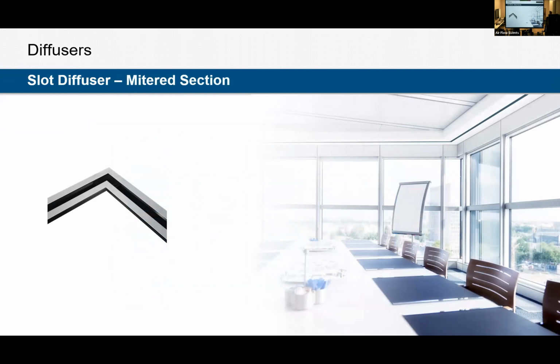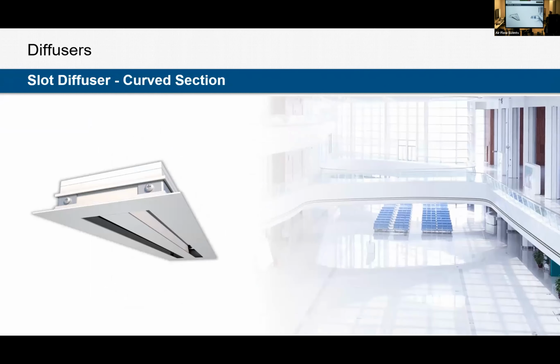Slot diffusers I mentioned are really nice for architectural spaces. So you can do fun things with the mitered corner to keep this continuous look. Or we can even curve the slot diffuser. In this bulkhead right here, it's a little hard to see, especially on this screen right now, but that bulkhead does a little bit of waving, and you could put a slot diffuser in there that matches it, whether it's concave or convex. You could also take a slot diffuser and curve it this direction. So maybe on a ceiling, you've got a wavy bulkhead that you want to match the curvature of. You could do all of that with curved slot diffusers. So very architecturally friendly.